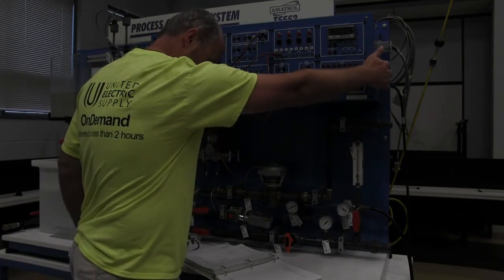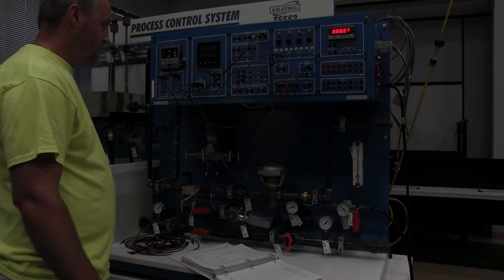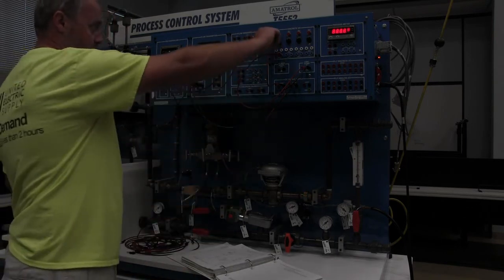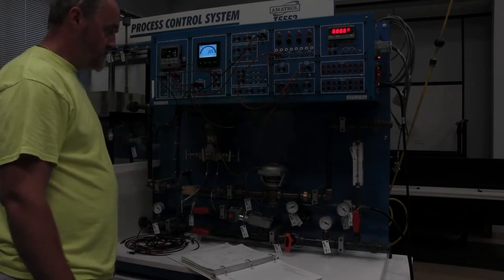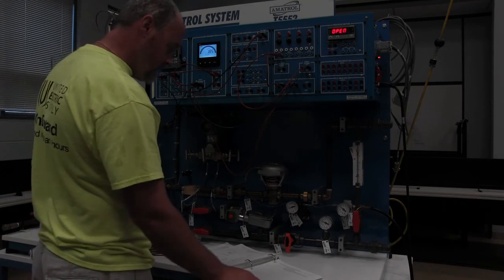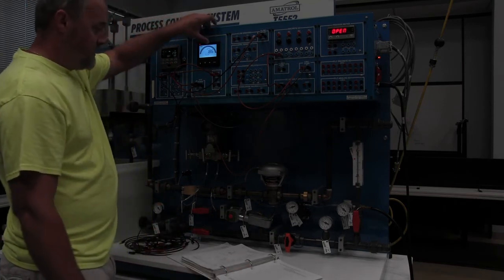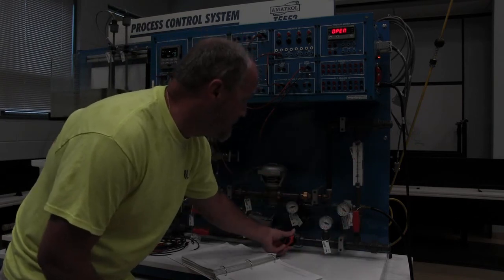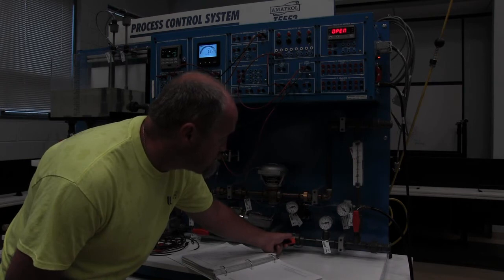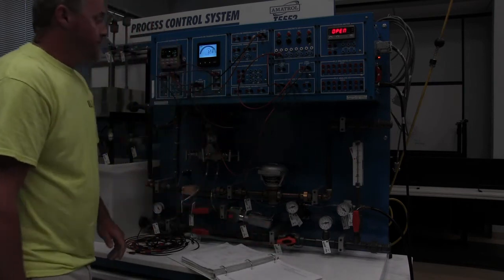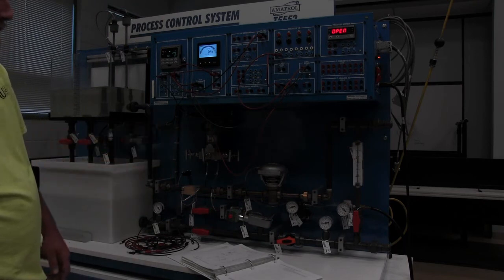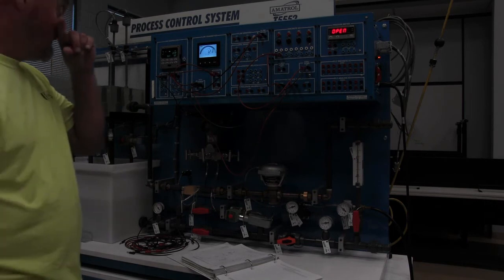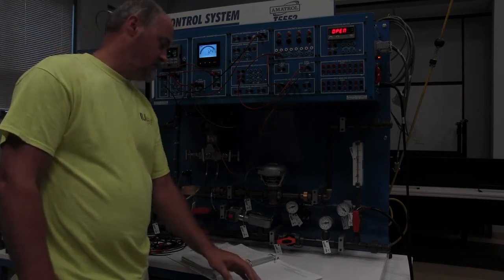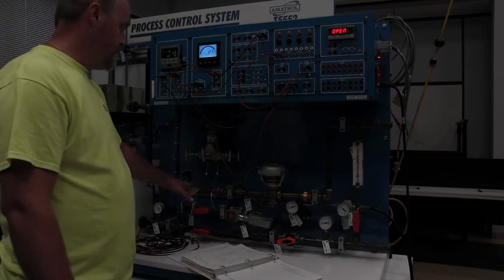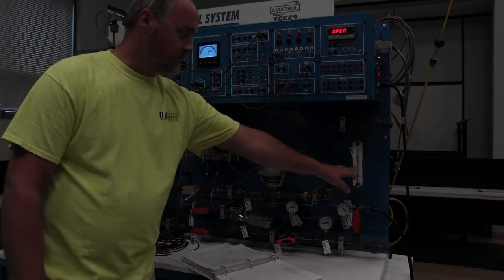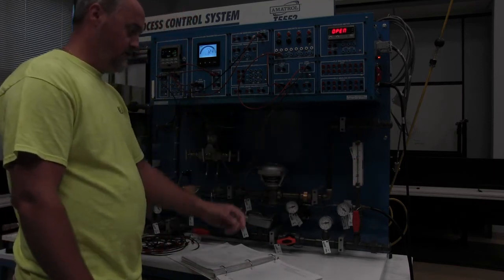So we're going to turn the main circuit breaker on. Once everything boots up, we're going to turn selector switch 1 on. When selector switch 1 comes on, I'm going to back this down just a little bit to give me a reference. So I have about 1.3 gallons on the rotary meter, and I have 1.23 on here. So you can see that they do jive up, that this meter is reading basically the same as what's going through the rotary meter.